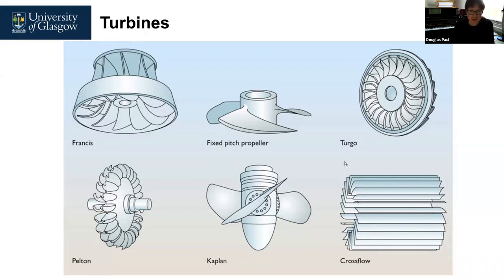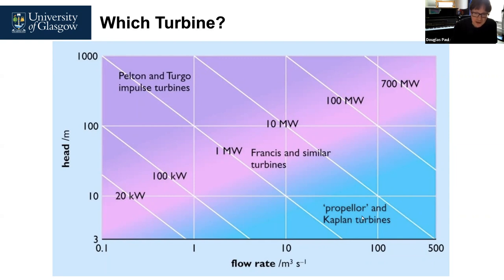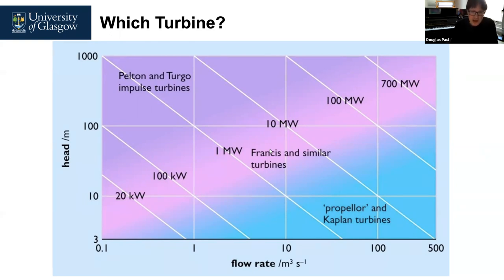There are many different turbine designs — one slide shows six examples — with many varieties used in different countries. To choose the right turbine: a high head of water calls for a Pelton or Turgo impulse turbine; a low head with very high flow rate uses a propeller-type or Kaplan turbine; and something in between uses the Francis turbine, which combines both reaction and impulse.